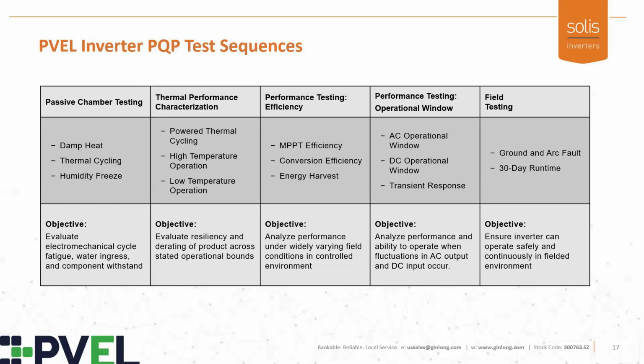When we get into the performance category, this includes things like maximum power point tracking efficiency, conversion efficiency, and energy harvest. For the MPPT efficiency, we test to the EN 50530 standard, where we're trying to understand the capability of the device to dynamically track the irradiance and temperature coefficients of the interconnected strings. Conversion efficiency and energy harvest are both additional tests that really allow us to understand how good this inverter product is at capturing the theoretical available energy on that given array.